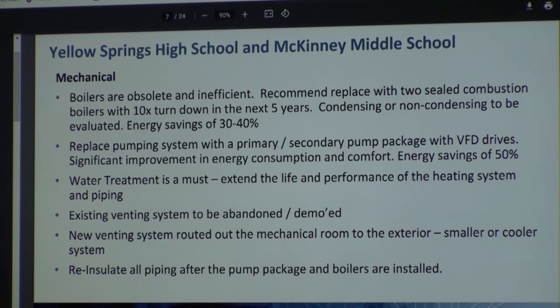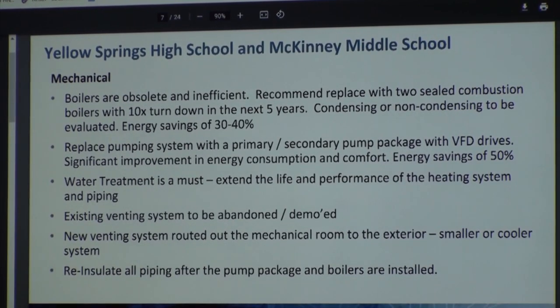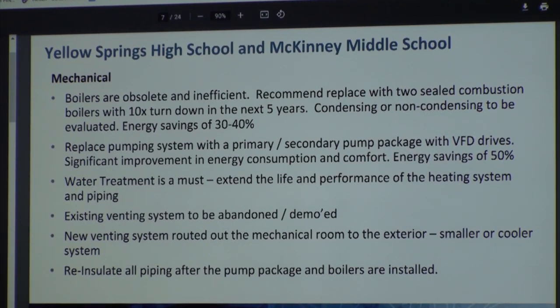So the flue is a brick chimney that goes up through the three stories. So it goes out in that wall and then turns and goes into the side of the chimney? Yes, okay. The chimney - you could run a high efficiency boiler into the chimney. If you put in a non-condensing boiler that's close to condensing, by the time the flue gases get out of the chimney, it's condensing, so you could end up destroying your chimney. Right, so is it lined? I can't imagine it is. No, it's not. So that's a consideration - if you can find a way to get directly outside of the building, that's probably better if you're using a condensing boiler. Correct.